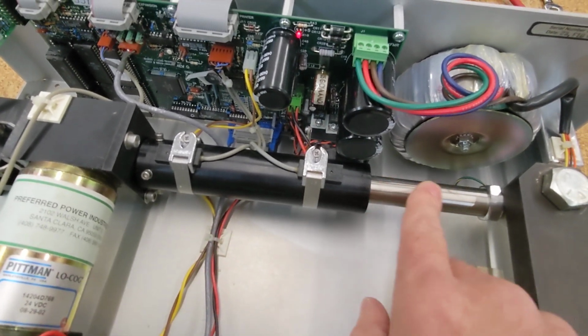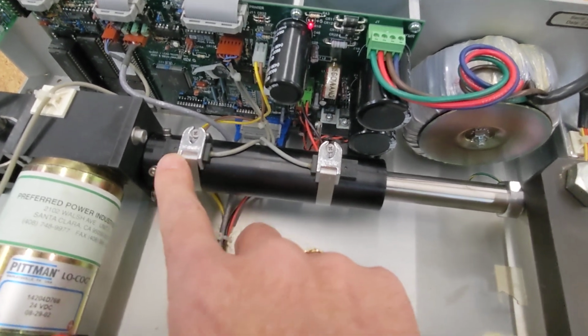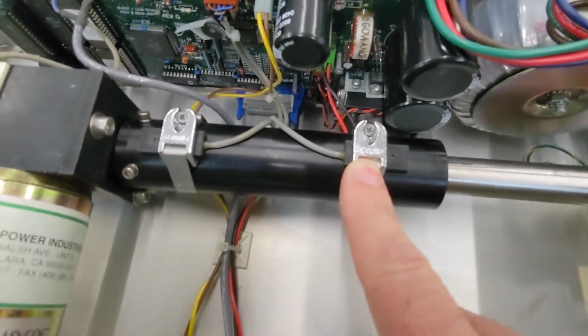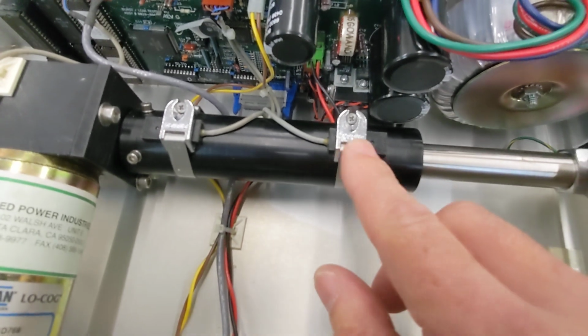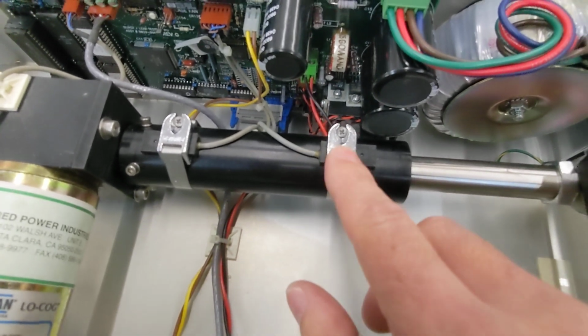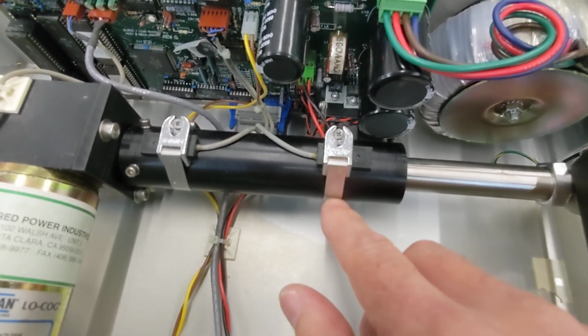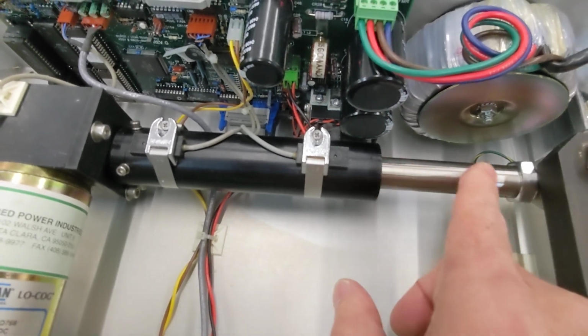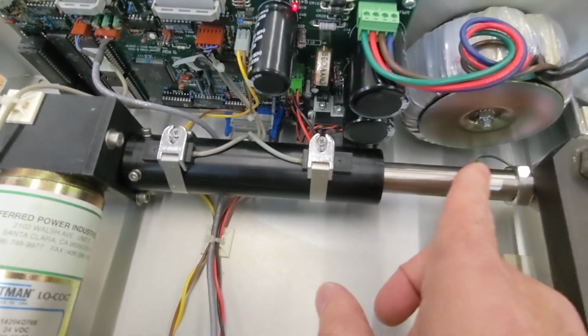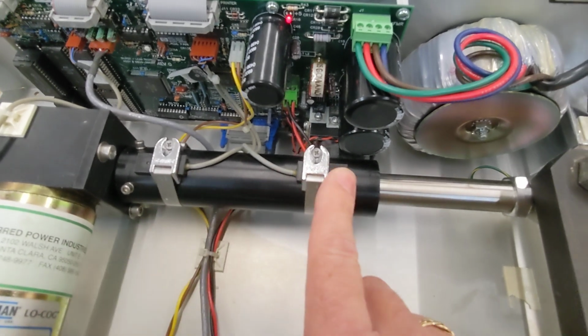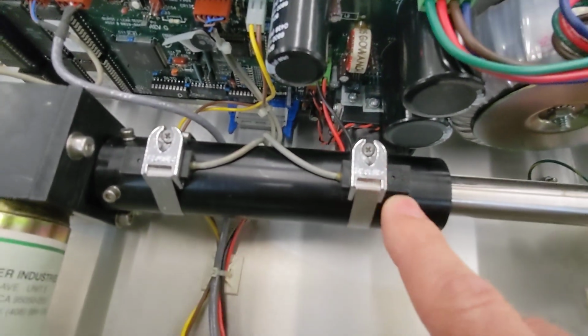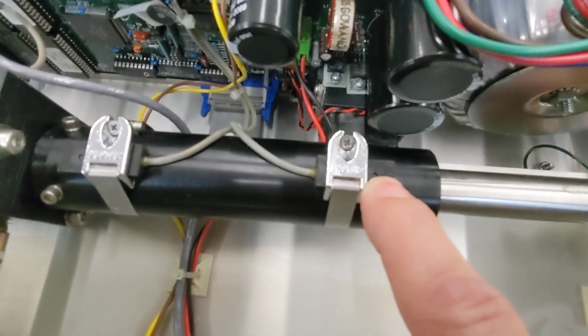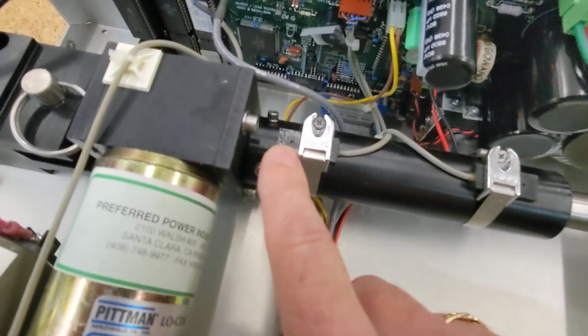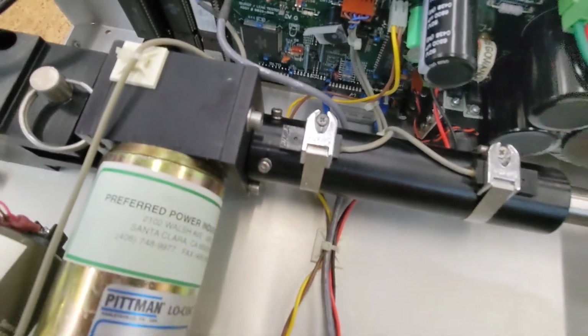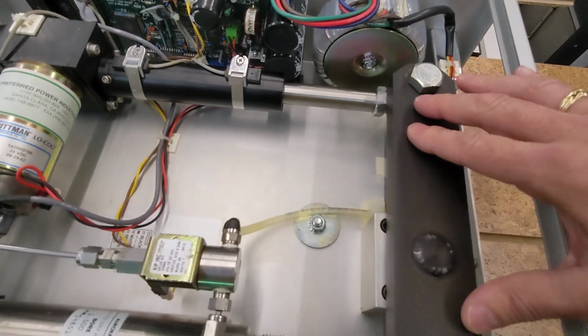This rod goes in and out. These are limit switches, made by Bimba. They would normally get stuck on the outside diameter of a Bimba air cylinder, but they're being used here as magnetic sensors to see where this position rod is. So when the rod is all the way back, we'll see that sensor tripped, and when it's all the way forward, we'll see this one tripped. There's an LED right above my finger, and one on this sensor too, so we'll see those go on.